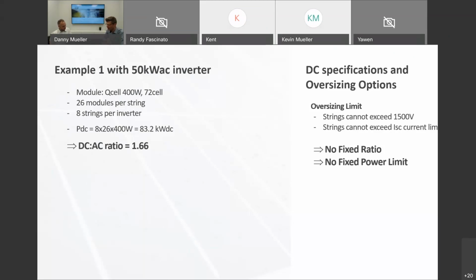Huawei, with one other company, are the only inverter companies who have no fixed DC to AC ratio in their documents, and also no fixed power limit you can connect to the inverter. The criteria for what you can connect is solely focused on the maximum string length based on voltage, so you cannot exceed the 1,500 volt string design, which is obvious, and you cannot exceed the short circuit input current of the inverter. With the 45 KTL and the smaller ones, you have per MPP tracker 30 amps ISC available.